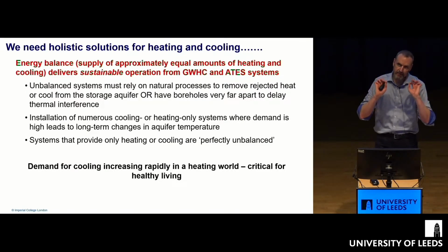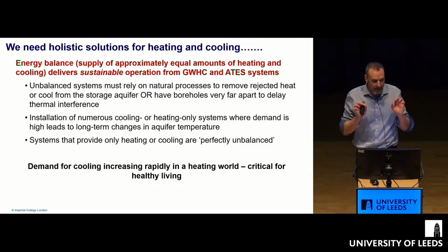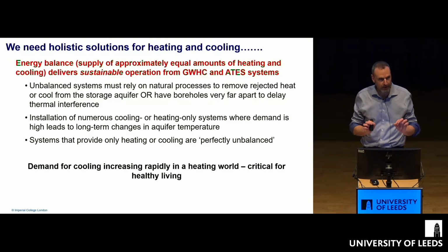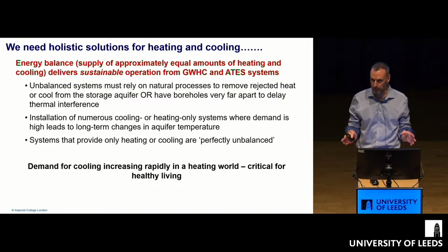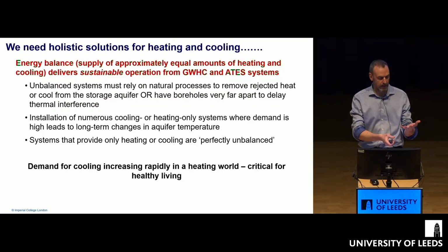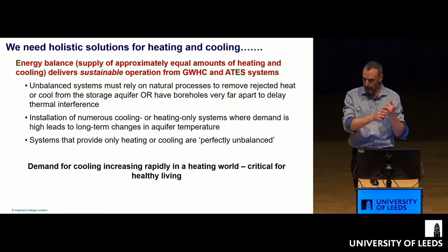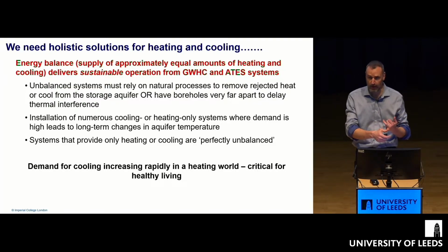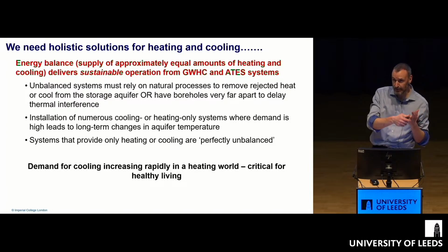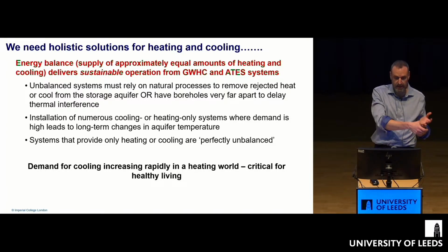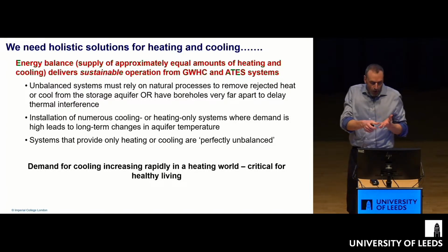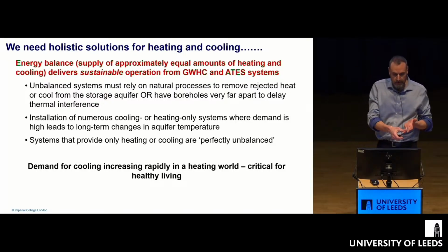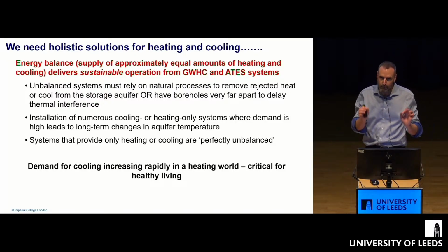One of the things I'm going to emphasize is that we really need holistic solutions for heating and cooling - they tend to be looked at as separate problems. We think about supplying heating with boilers if we're happy to burn gas, or dedicated ground source or air source systems for heating. If we're going to operate groundwater systems though, what's really useful is having what's called energy balance - that means we extract and inject equal amounts of heat and cool into the subsurface.